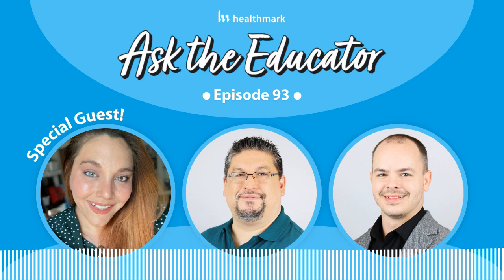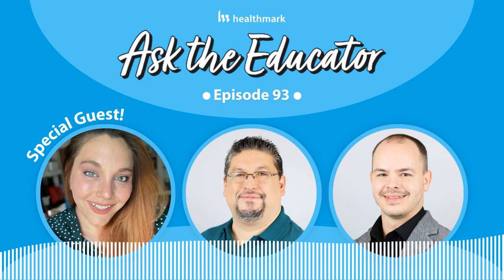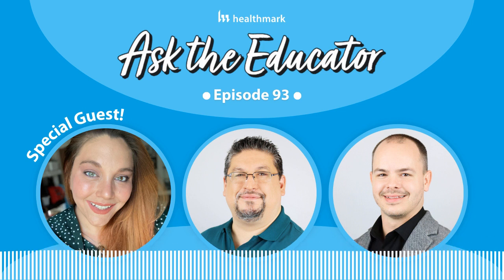I know we've done some internal testing here at Healthmark to figure out what those are, but I'm sure it's something that you as a customer could reach out to the manufacturer of the insulation tester and find out exactly how many kilovolts are coming from the low setting or how many are coming from the high setting. Either way, it's good to know that. But if you have instruments in your inventory that require a 1.5 setting, then unfortunately you're not going to have the flexibility to set it there with some of those insulation testers that are out there. So that's something that people really need to be aware of as they build their program out.